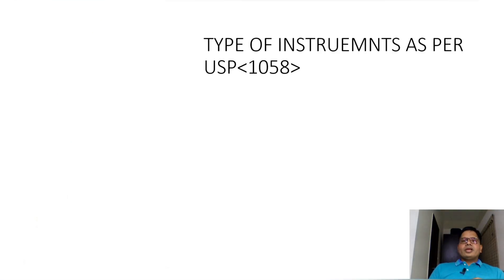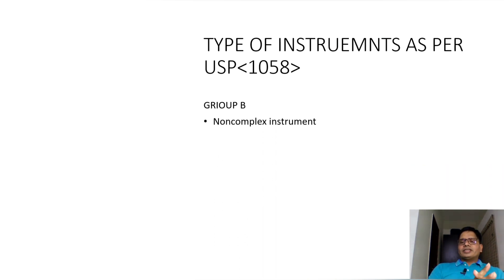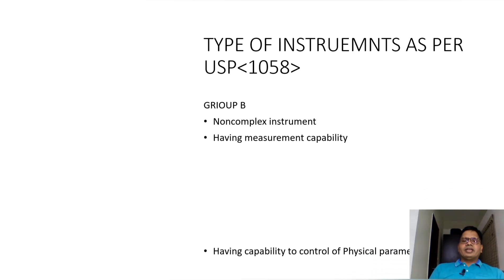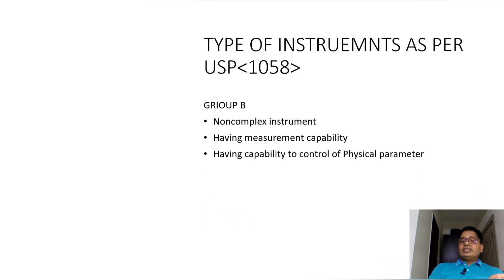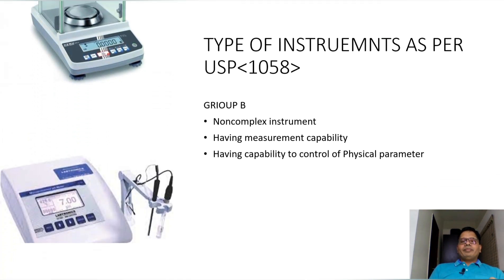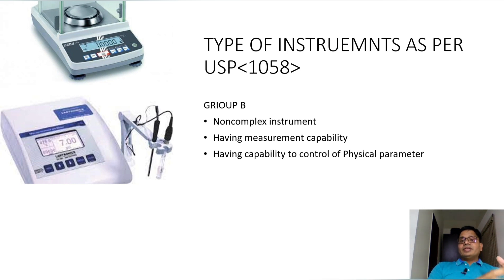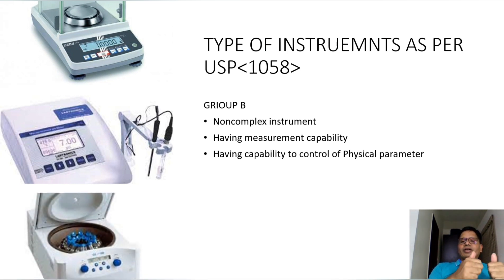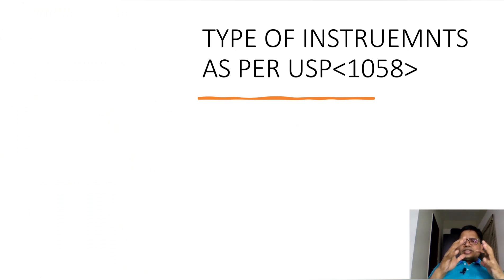As per USP 1058, the second group is Group B instruments — non-complex, simple instruments that have measurement capability. They can measure data, and they have the capability to control physical parameters such as temperature, pressure, and humidity. Examples include a balance and a pH meter — these are not attached with a computer, but they have the capability of measurement, so they come under Group B instruments.